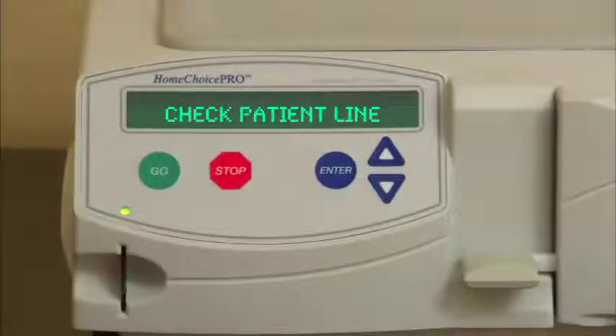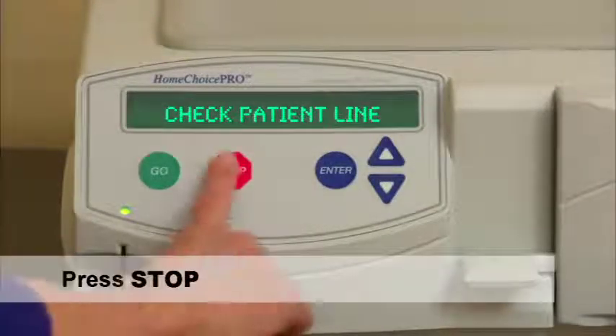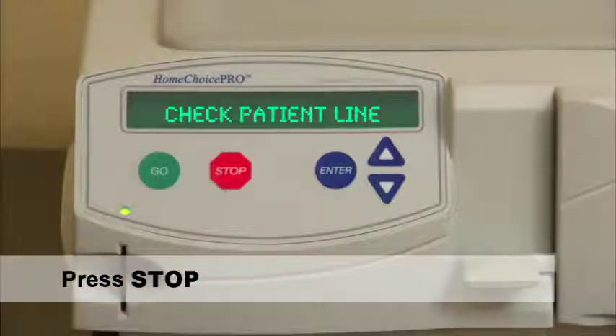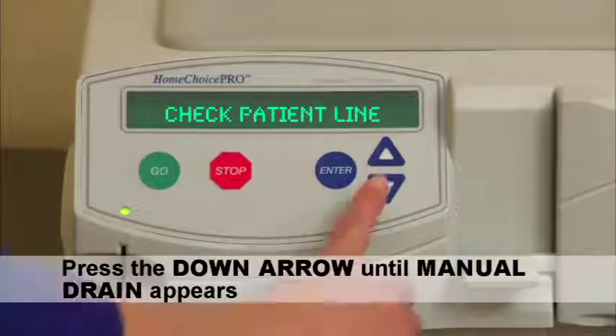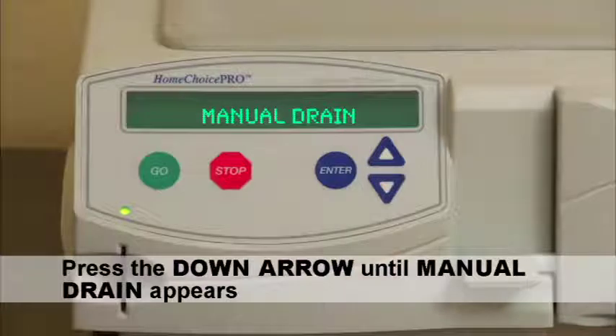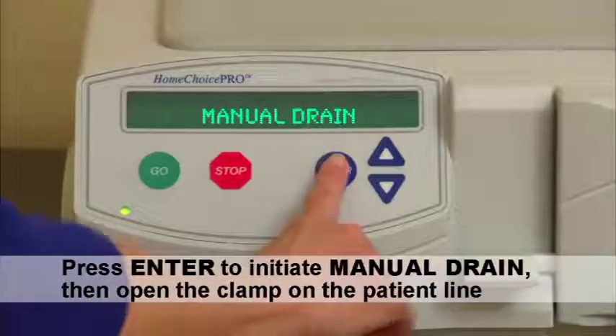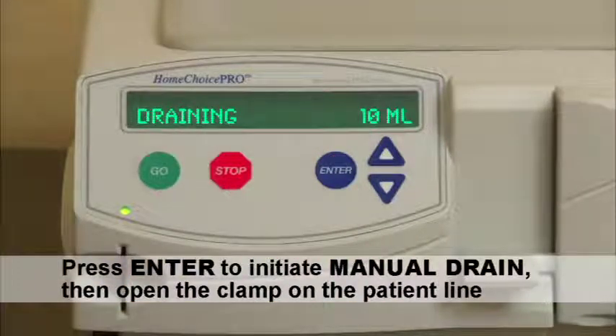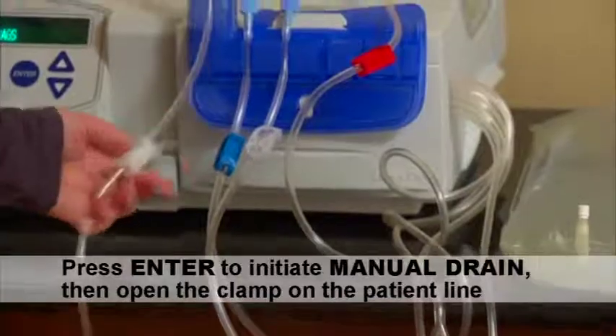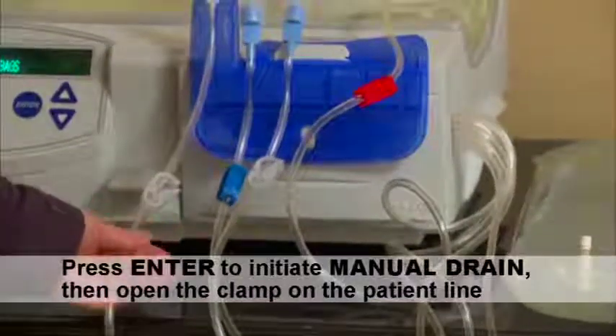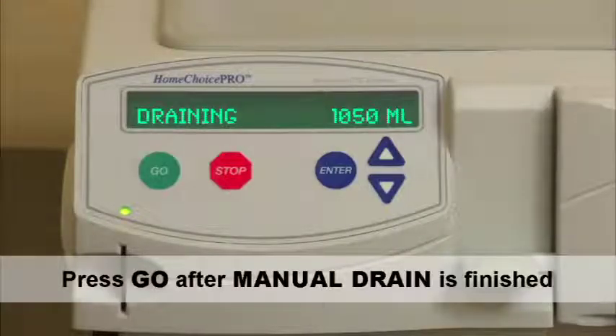If cause number 2 occurs, press stop. Press the down arrow until manual drain appears, if it is not already displayed. Press enter to initiate manual drain. Then open the clamp on the patient line. Press go after manual drain is finished.